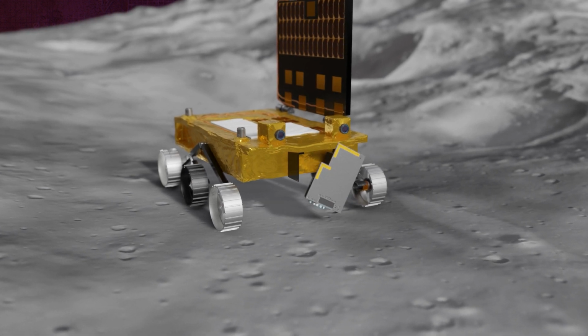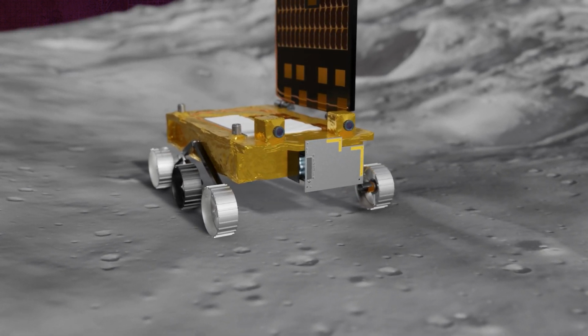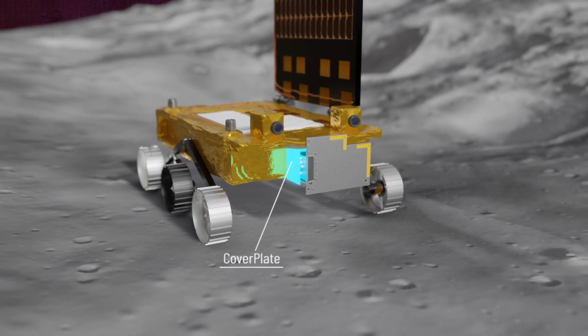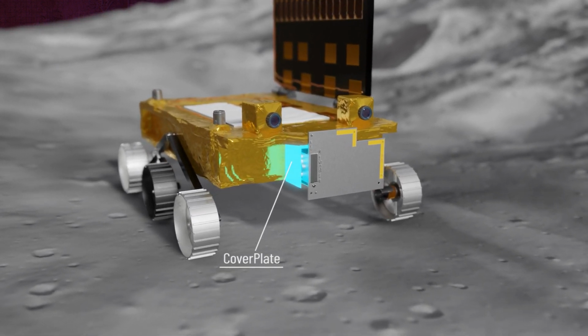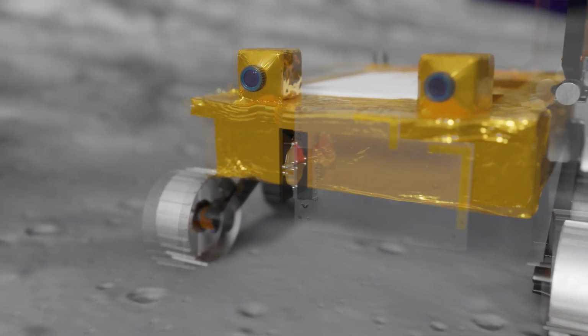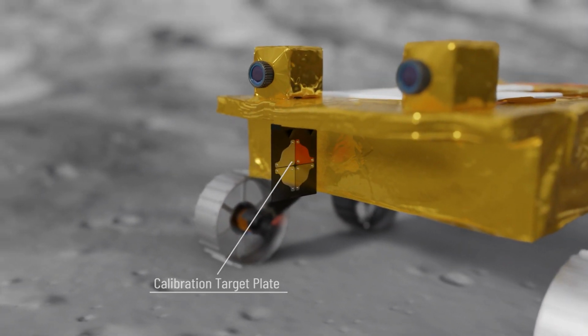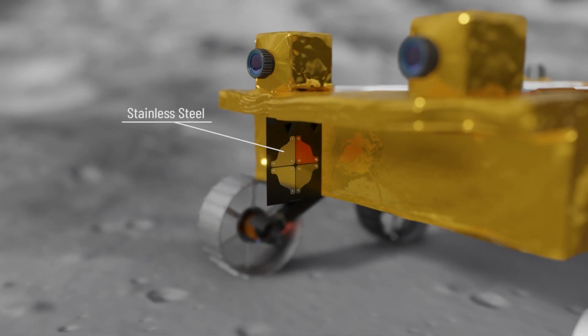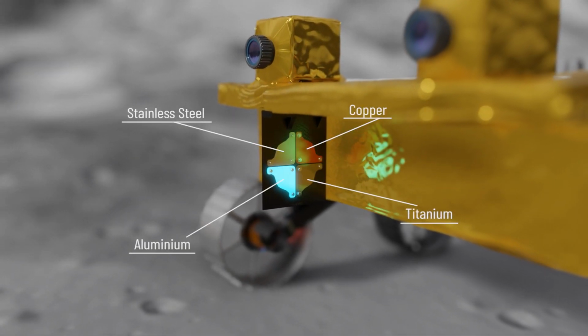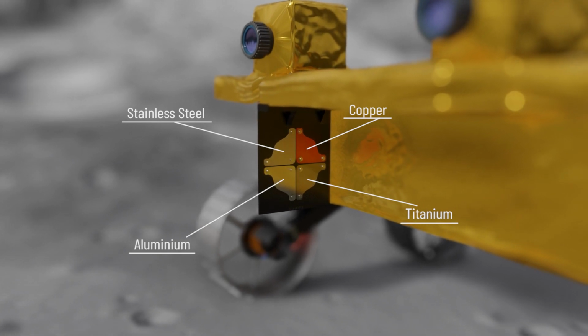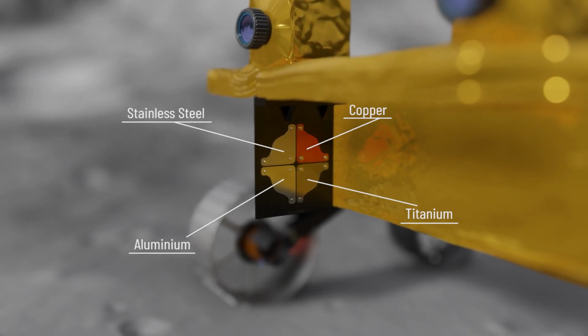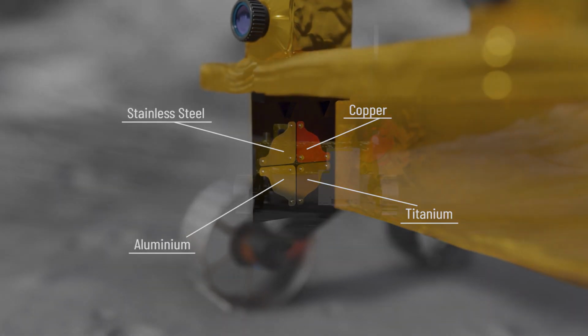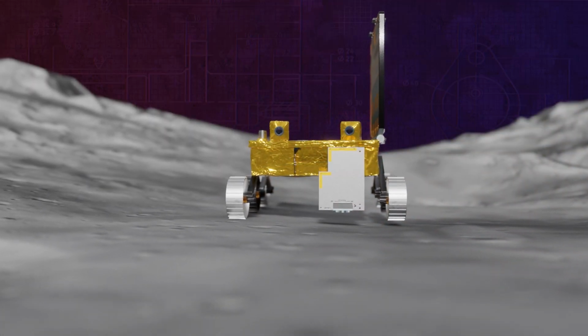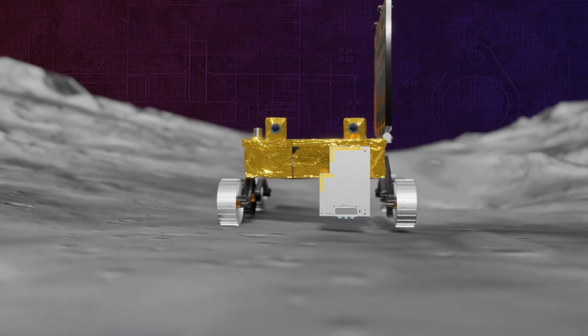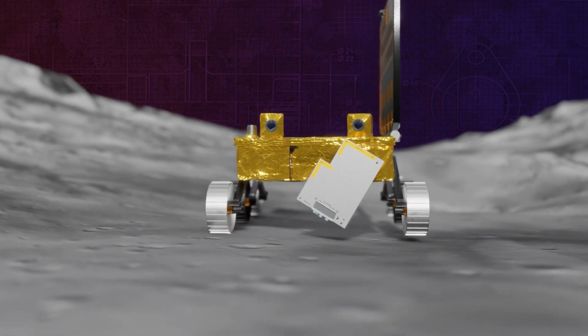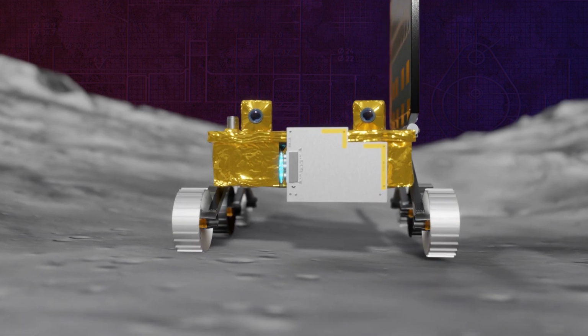When not in use, to save the instrument from lunar dust and debris, sensitive parts of the instrument are covered by a cover plate. This cover plate is also a calibration target plate. The plate has 4 elements attached to it: stainless steel, copper, titanium, and aluminium. It is used to calibrate the instrument before use, to make sure the readings taken by the instrument are accurate. The instrument is open to the lunar dust and debris when the readings are taken, and it can be retracted to increase the rover's ground clearance while moving.